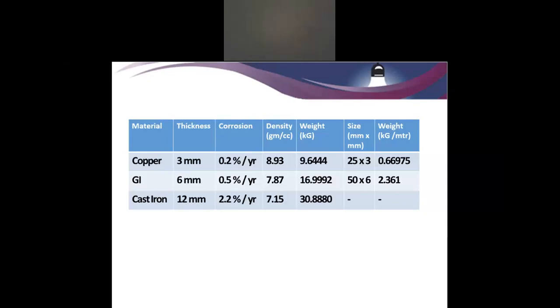So we got cast iron. We have taken more thickness, taking care of corrosion effect, and it acts as a very good conductor when the cast iron is not painted or galvanized; cast iron acts very wonderfully in the soil. There is definitely a corrosion effect, and it's more, but considering higher thickness, it gives around 100 years of life.